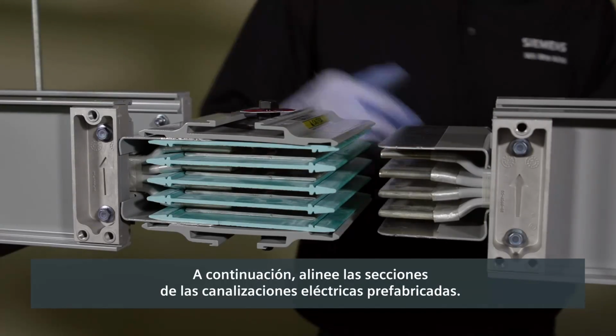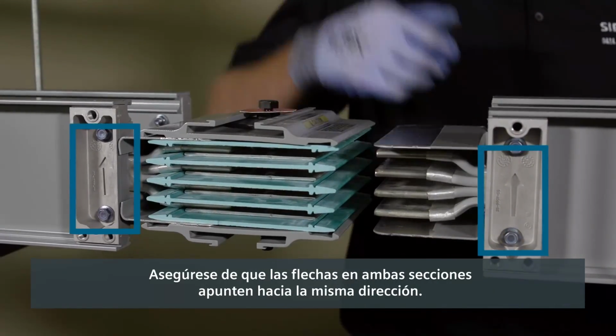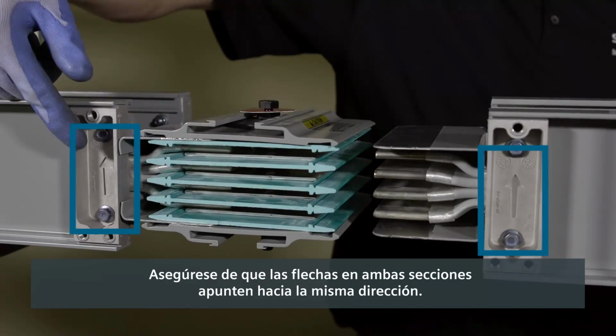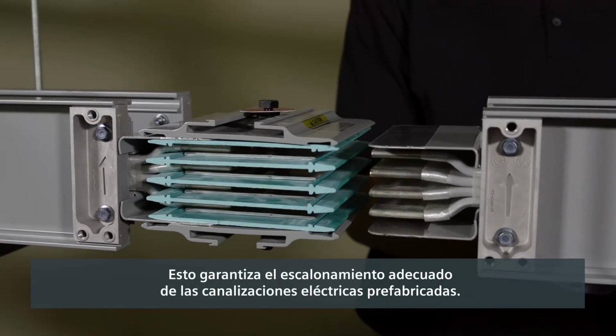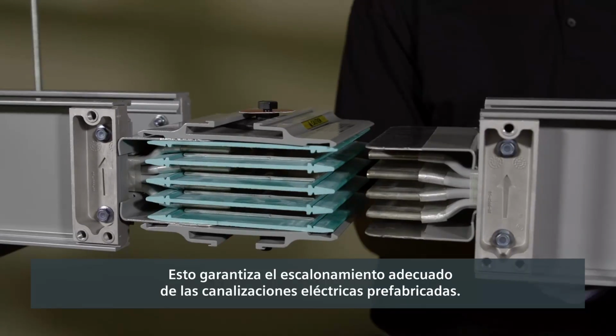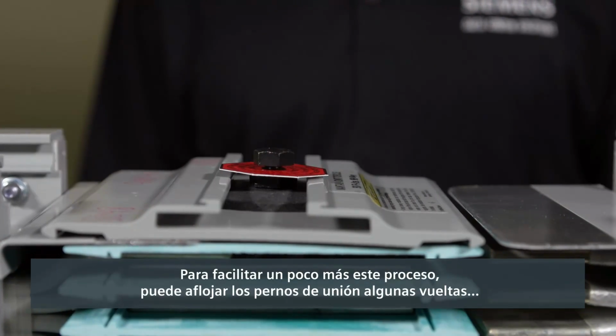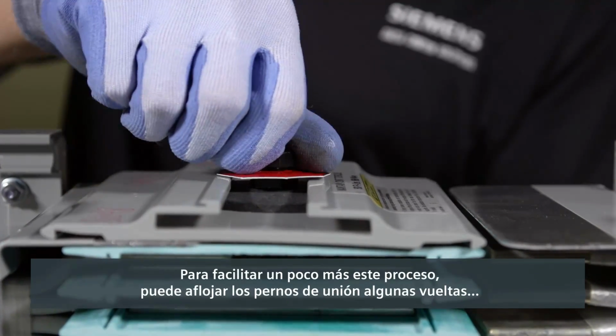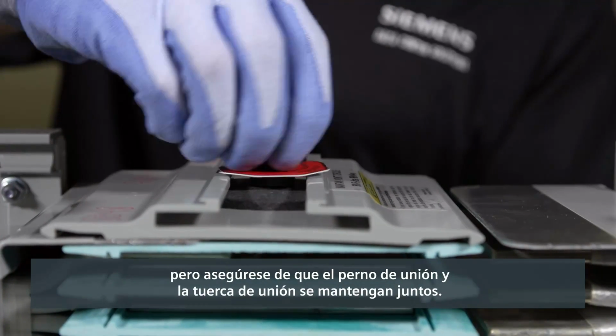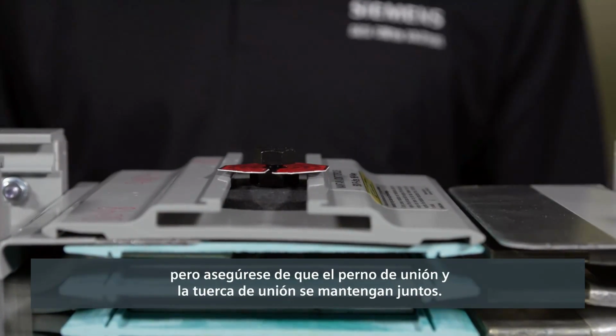Next, align the busway sections. Make sure the arrows on both sections point in the same direction. This ensures proper phasing of the busway. To make this process a little easier, you can loosen the joint bolts a few turns, but be sure the joint bolt and the joint nut stay together.